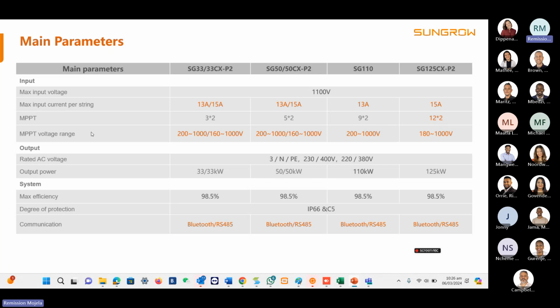And then the MPPT operating range for the 33 is a minimum of 200 volts, and the 33 P2 is 160. For the 50 it is the same, and for the 110 it's 200 as well. Compared to the old CX versions, it is 200 to 1000, except for the P2 versions, which are 160 to 1000, except for the 125, which is 180 to 1000. And our systems can all work in basically all three grounding systems. It can work in IT, TT, and TN, depending on how your connection on that particular site is.